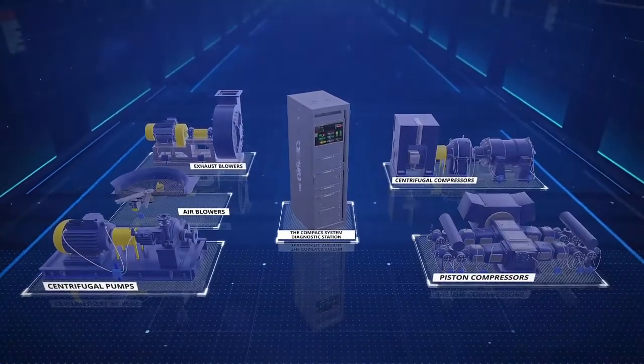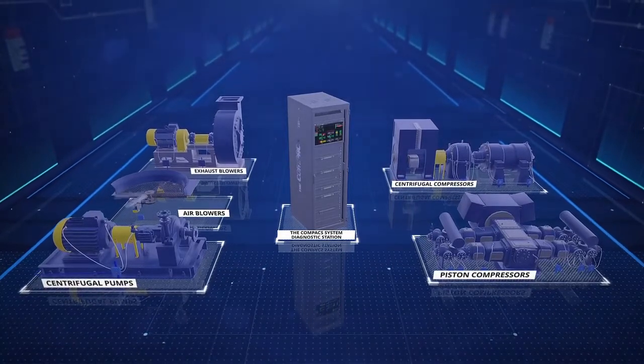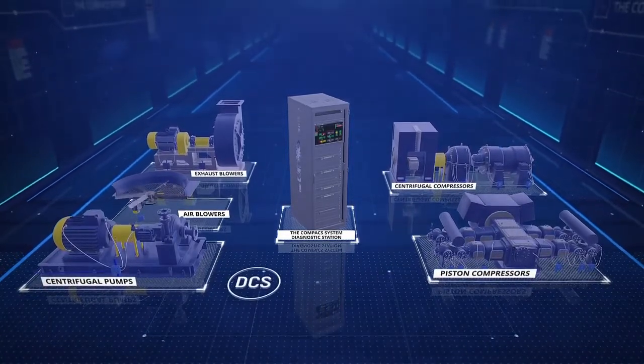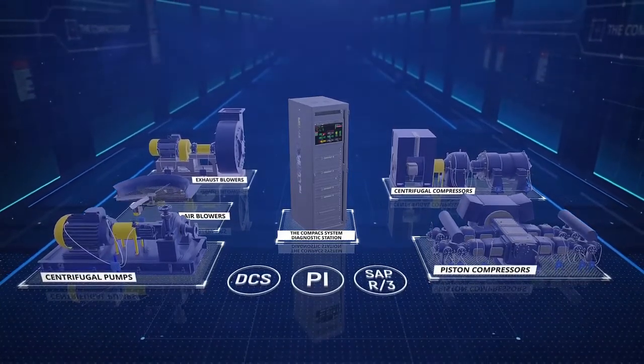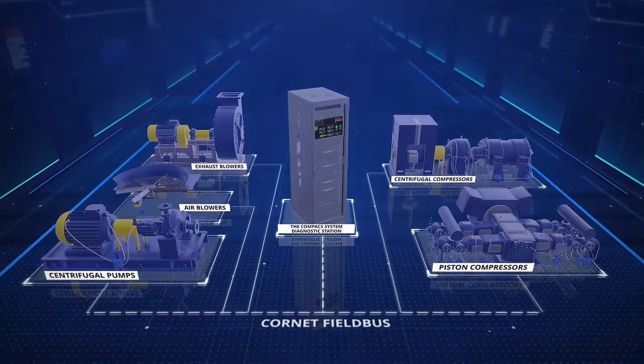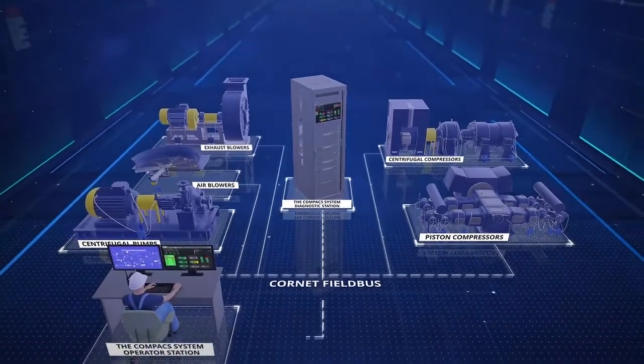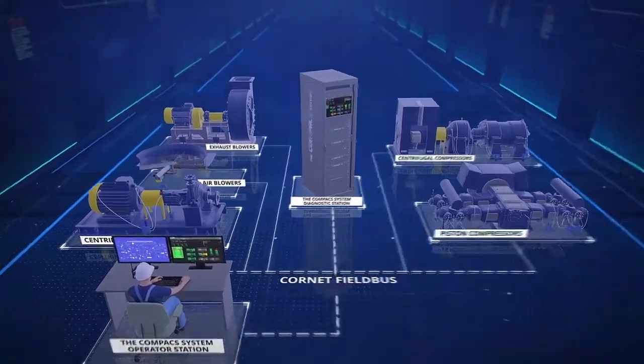The diagnostic station is located in the control room and, using a single hardware and software platform, can be integrated with the DCS, PI, SAP R3, and other systems over either Modbus or OPC interfaces. The SCADA-type field bus gathers proper data for the physics-based AI, which transforms sudden defects into gradual ones and warns personnel by prescriptions on what actions need to be taken to prevent a failure and keep a machine running.